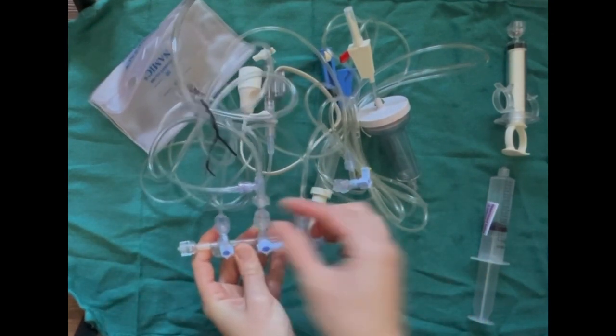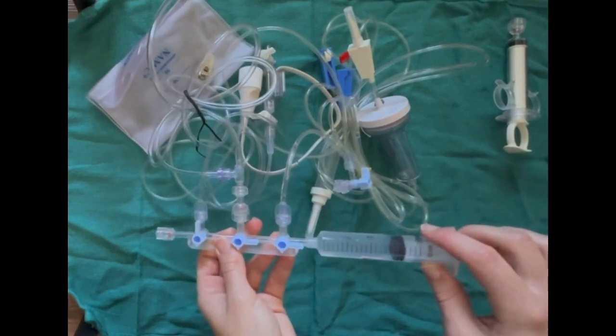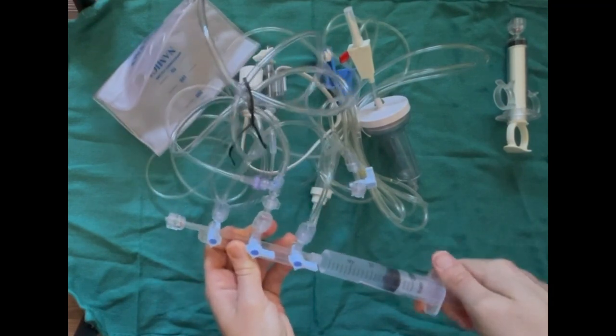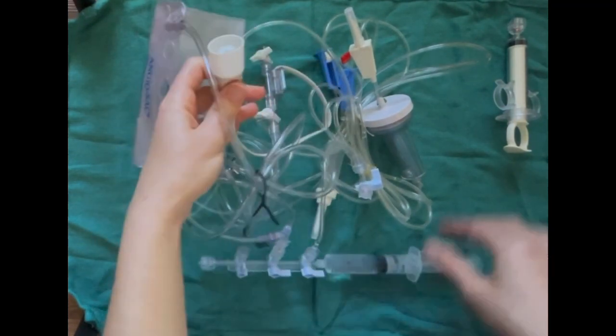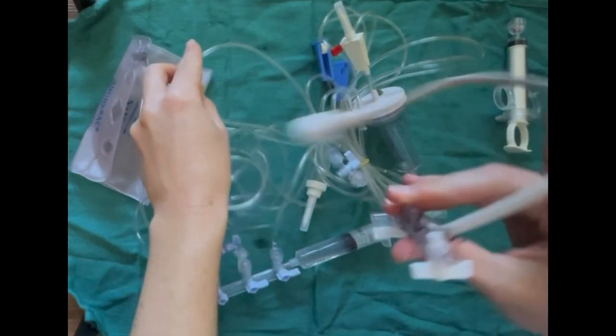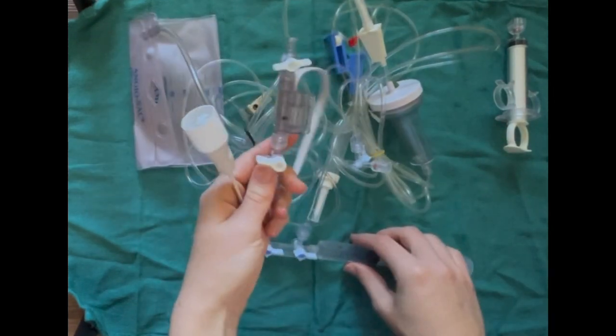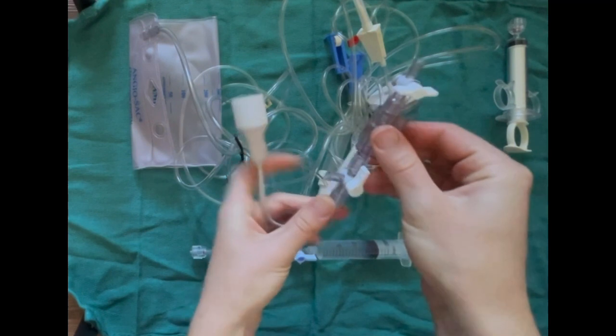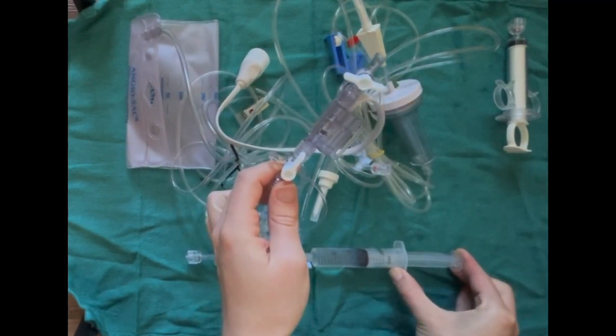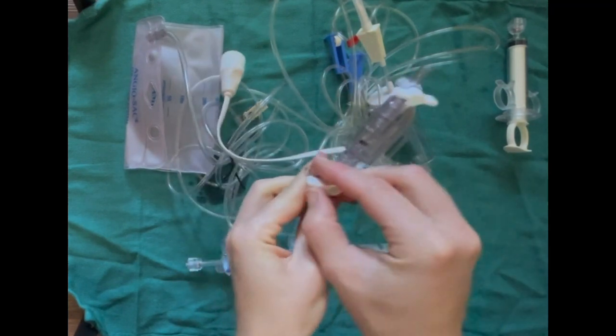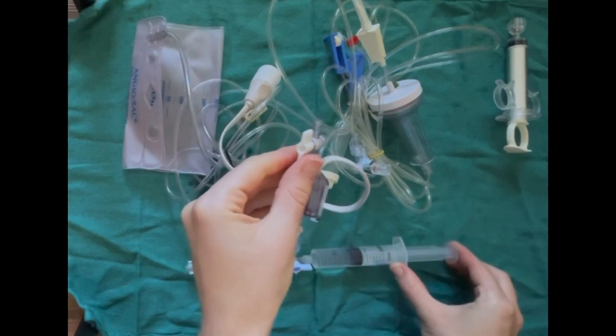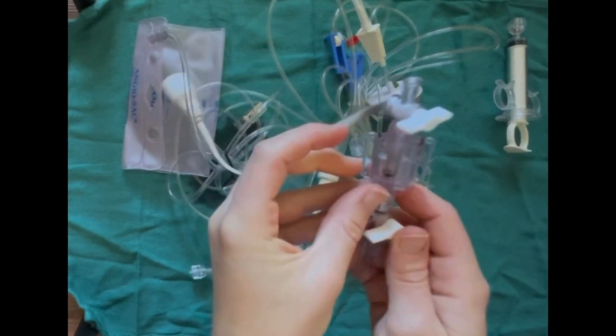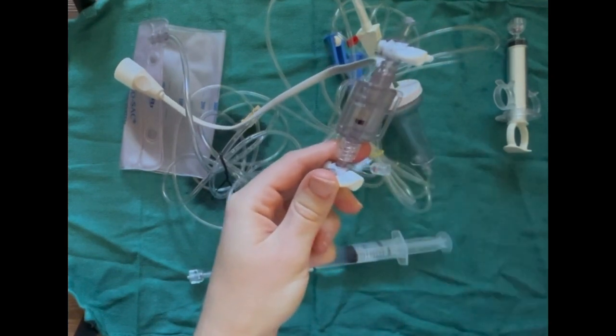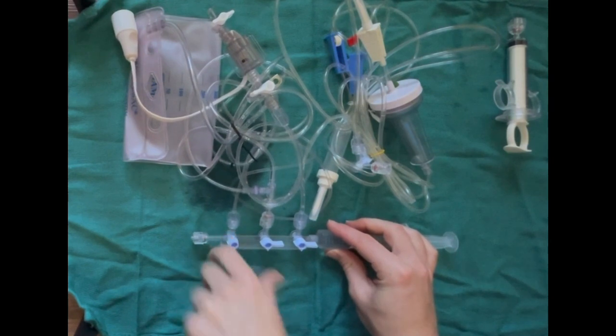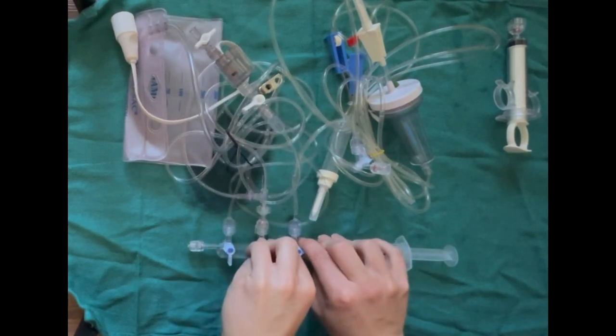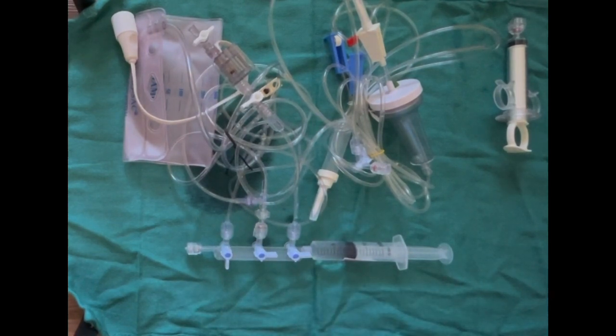Make sure that all your ports are tight before you push any saline. And then the first thing you're going to do to prepare it is flush through your transducer, which is your pressure monitor. Again, yours will be better organized than this, hopefully. So the first thing is the side port. That gauge right there that I just turned is off. So right now it's off to the end part, and you can see that saline came through the side. Turn it off while you're pushing saline, and then the same thing with this transducer. Push saline and turn it off. You can also tap it against the bowl while you do that, just to make sure you don't have any air bubbles right there in that area, because that can lead to improper pressure readings. Always make sure to turn it on to pressure, which is turning it down. And that's how you prep the manifold.